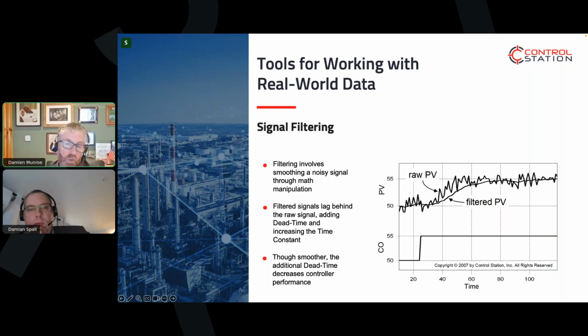Now, there's not a huge difference here, but it's arguable that on the raw signal, we moved in the upward direction much sooner than on the actual filtered line. So we're adding dead time to our perceived model. Dead time is the killer of good control. So we're lengthening the dead time, we're killing the ability to respond to it.